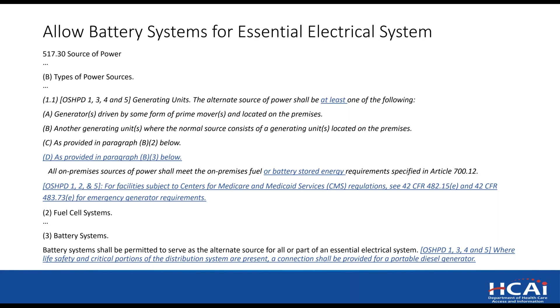So this is 51730, it talks about source of power for emergency, and we have a 1.1 that identifies the allowable sources, and we're adding in batteries as an acceptable EPS to match the model code. We have a pointer that talks about the requirement for CMS for batteries on premises, and we also include a requirement that if batteries are your EPS, a connection will be provided for a portable diesel generator. This is similar to the requirement that we see in the model code for fuel cells. Next slide.